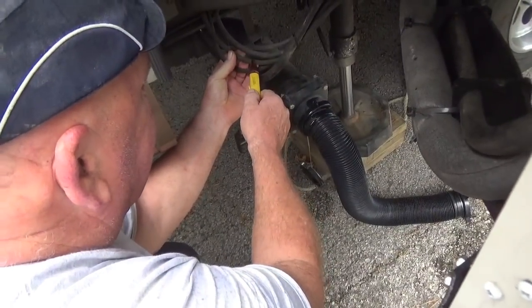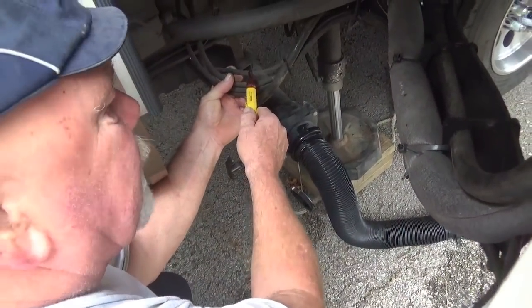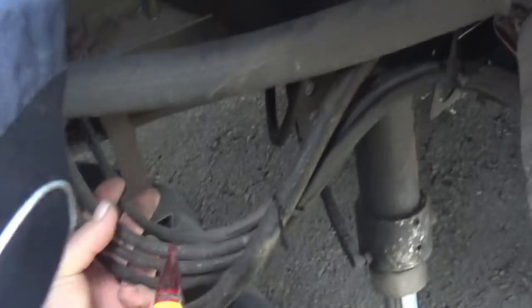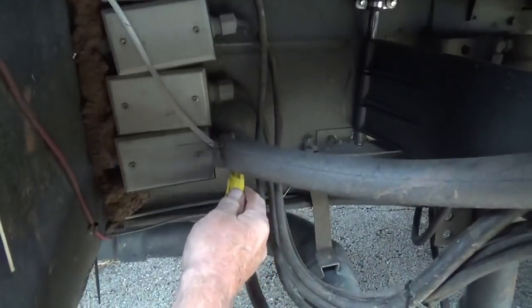Maybe it's one of these four — process of elimination. I've got a hot stick and it detects whether you have current going through a wire or not, instead of opening up all the boxes trying to guess. Since that circuit shut off, go through all the wires and the one that doesn't show juice is the target. You hold it up to a wire — detecting that one, detecting that one. Okay, that one goes to this box — this box is hot, that box is hot, that one isn't, that one's hot.